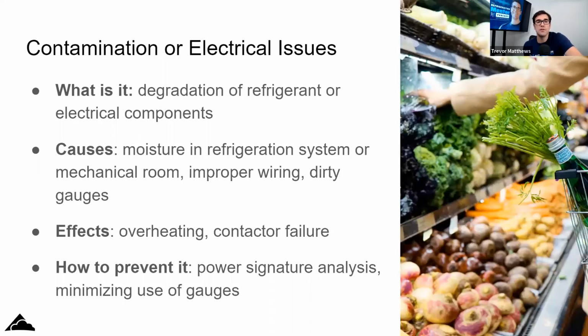So there's a kind of rule. It's an 80-20 rule. 80% of the time, the compressor fails by a mechanical failure. 20% of the time, electrical. But most technicians see it as 80% electrical failure and don't understand that it's a mechanical failure that caused that electrical failure. A true electrical issue would be like your contactor welded, or you got a failed contactor, or you got a rub through and it shorts the compressor out, or you're not wired up properly and you got a loose lug on there and it starts to arc.